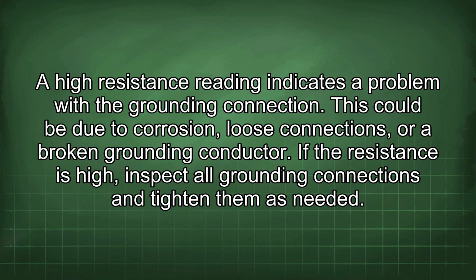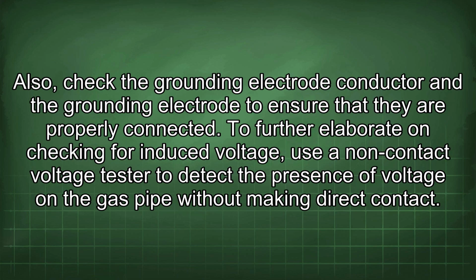If the resistance is high, inspect all grounding connections and tighten them as needed. Also, check the grounding electrode conductor and the grounding electrode to ensure that they are properly connected. To further elaborate on checking for induced voltage, use a non-contact voltage tester to detect the presence of voltage on the gas pipe without making direct contact.